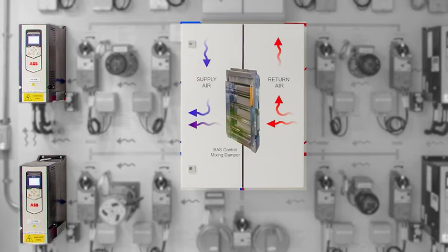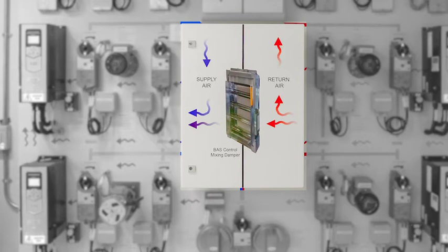In conjunction with this interface cabinet, the ACS 880 embedded adaptive programming software is used to eliminate the requirement for expensive relay logic control of damper actuators and damper status feedback. Expensive PLC IO points are minimized. In this way, PLC hardware costs were dramatically reduced. IO point cabling is eliminated, PLC programming time is reduced, and the DPU footprint is smaller by up to 50% in some cases.